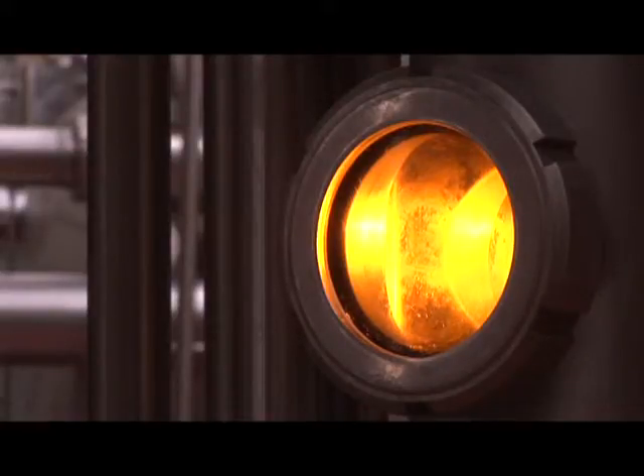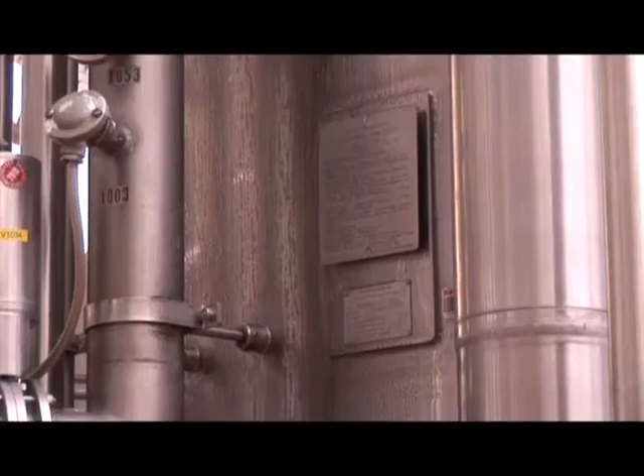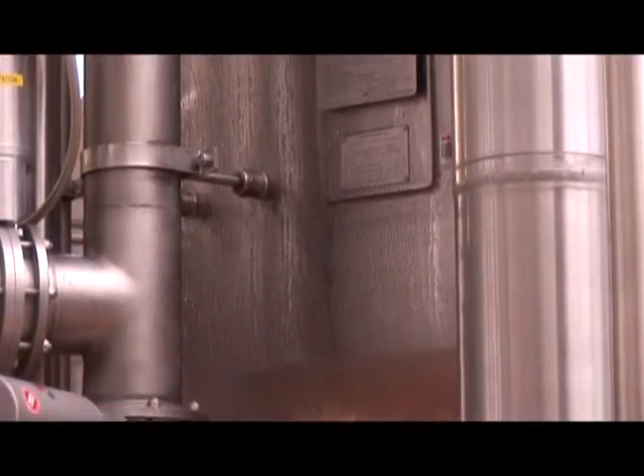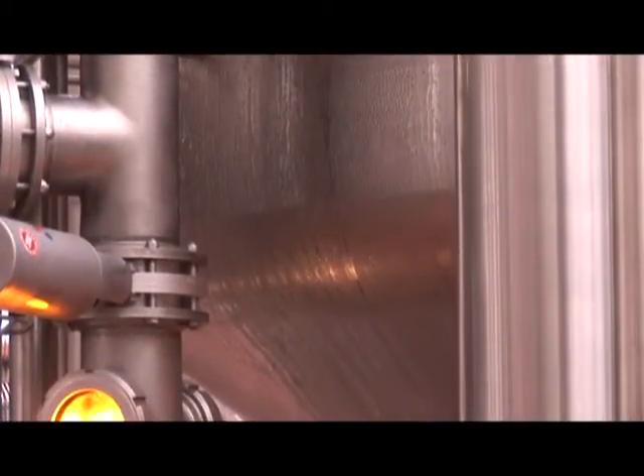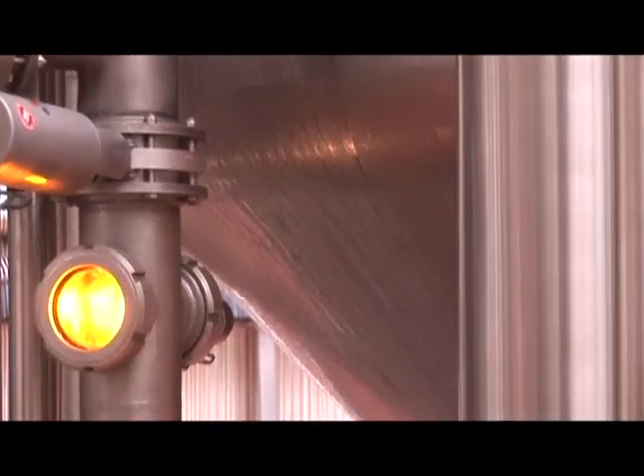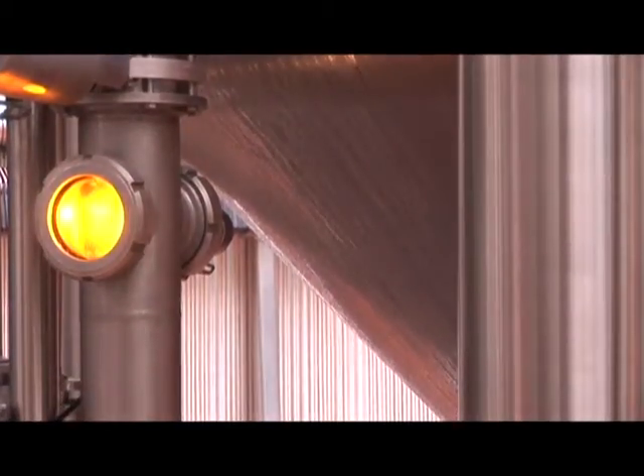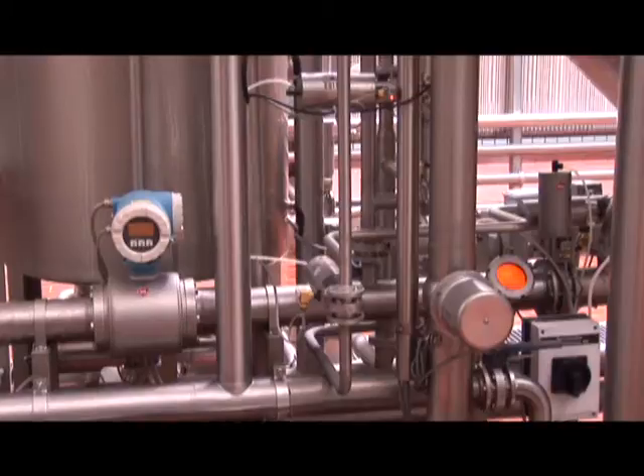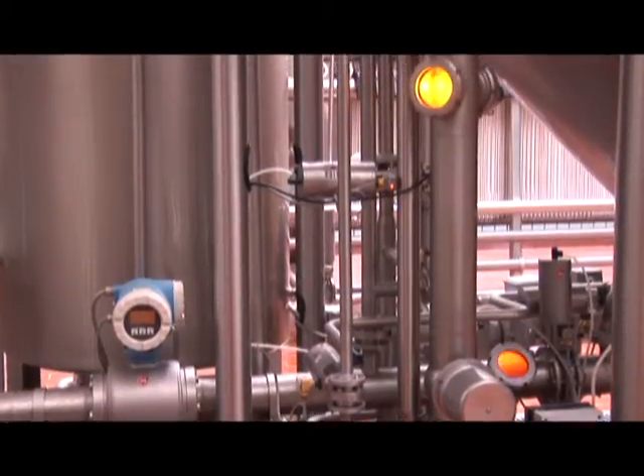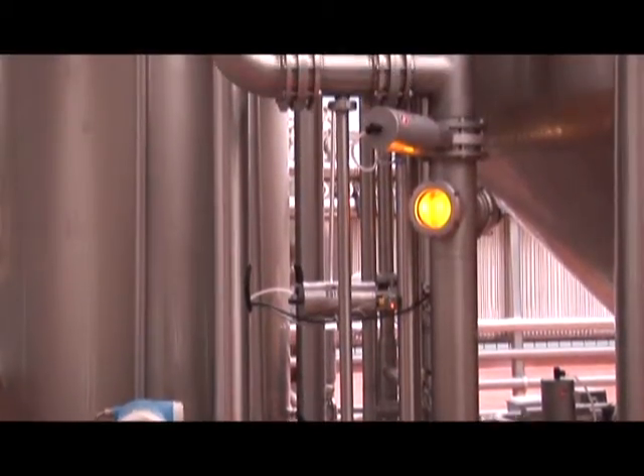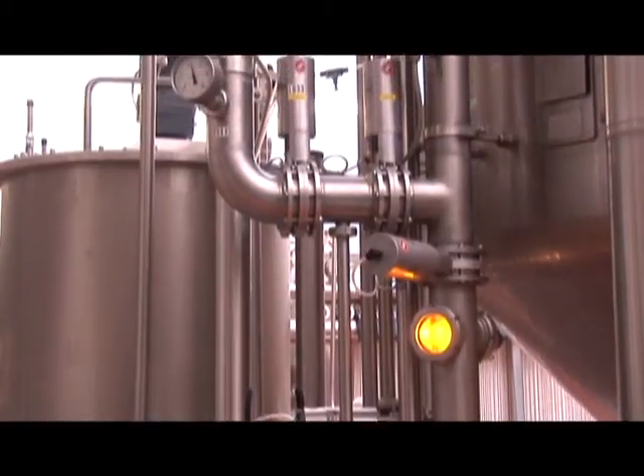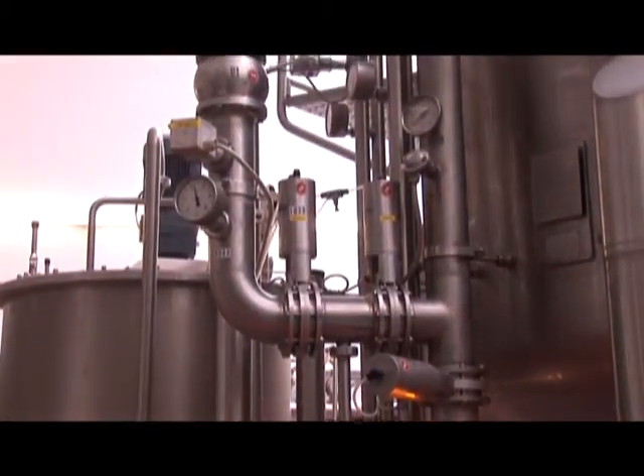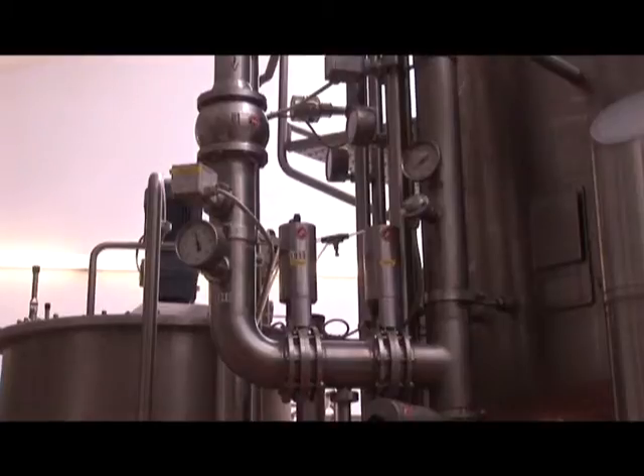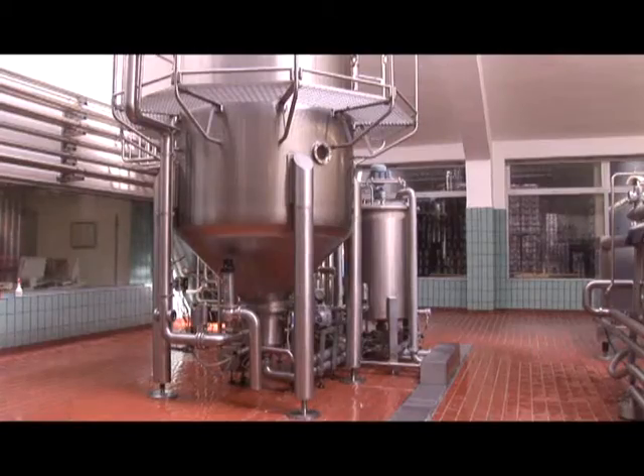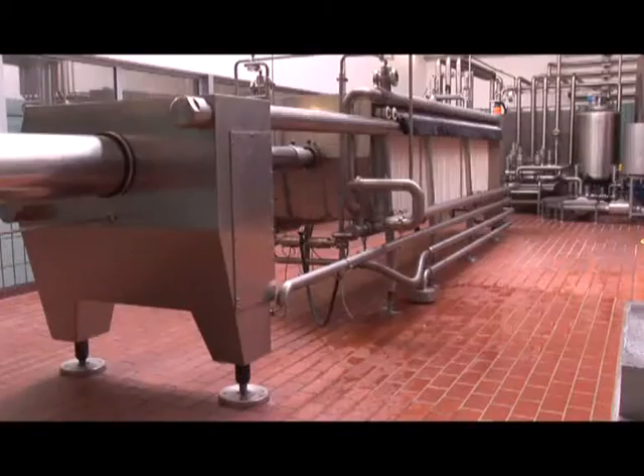With the start of beer filtration, the container is cooled to the filtration temperature of -2 to +5 degrees Celsius. One can very easily see the condensation on the filtration tank. The dosage vessel of diatomite has both a level measurement with the Delta Pilot FMB50, as well as a Liquiphant for empty notification and multi-cup overfill protection.